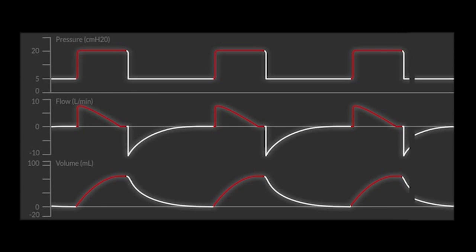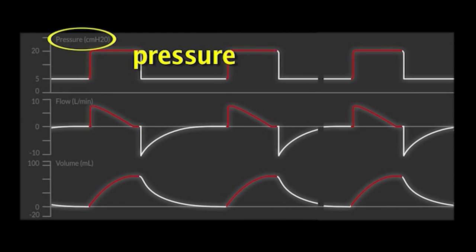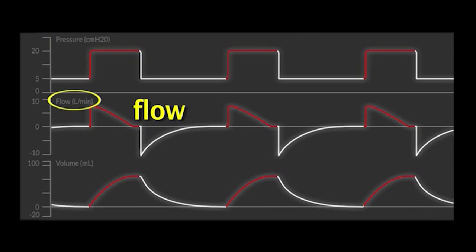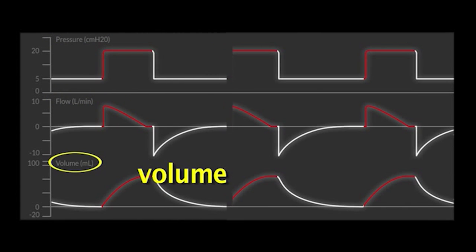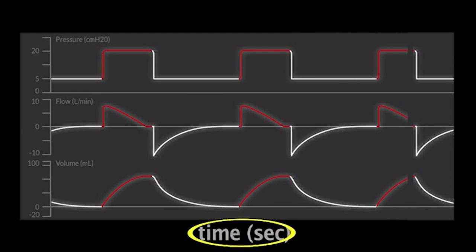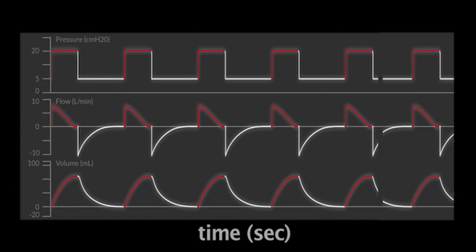Each of these three waveforms has a different vertical axis depending on which you are looking at. For pressure, it is going to be in centimeters of water, a unit of pressure. For flow, it is typically displayed in liters per minute, and we have a positive and a negative. And then finally the volume is just a volume unit, either mLs or liters. On the horizontal axis, time is typically displayed in seconds and you can adjust this to display more or fewer breaths depending on how much information you have set to display at a time.